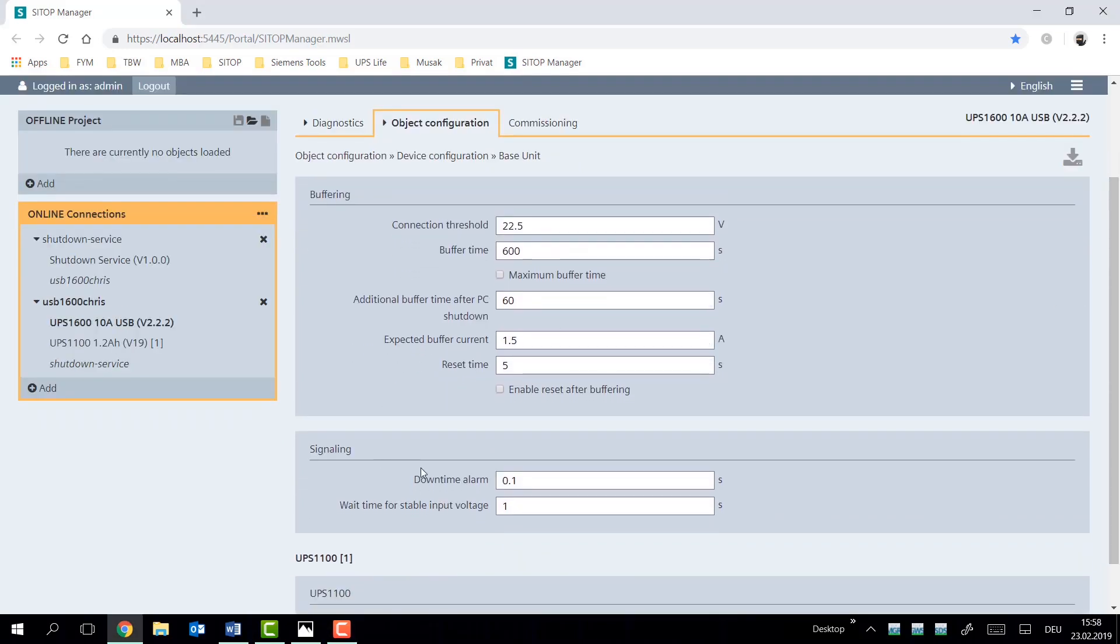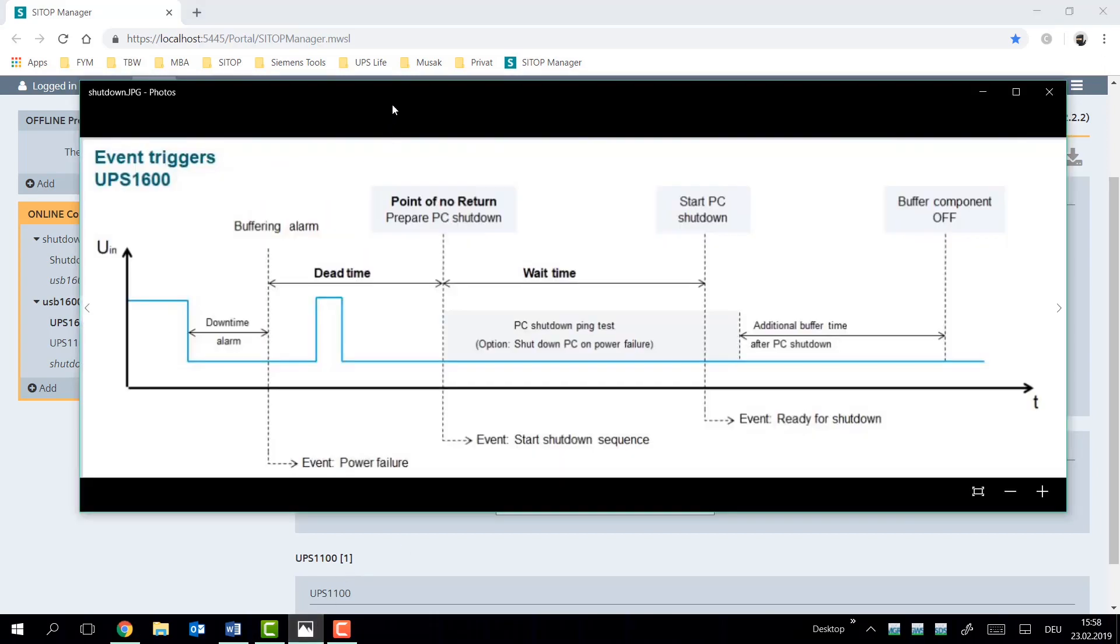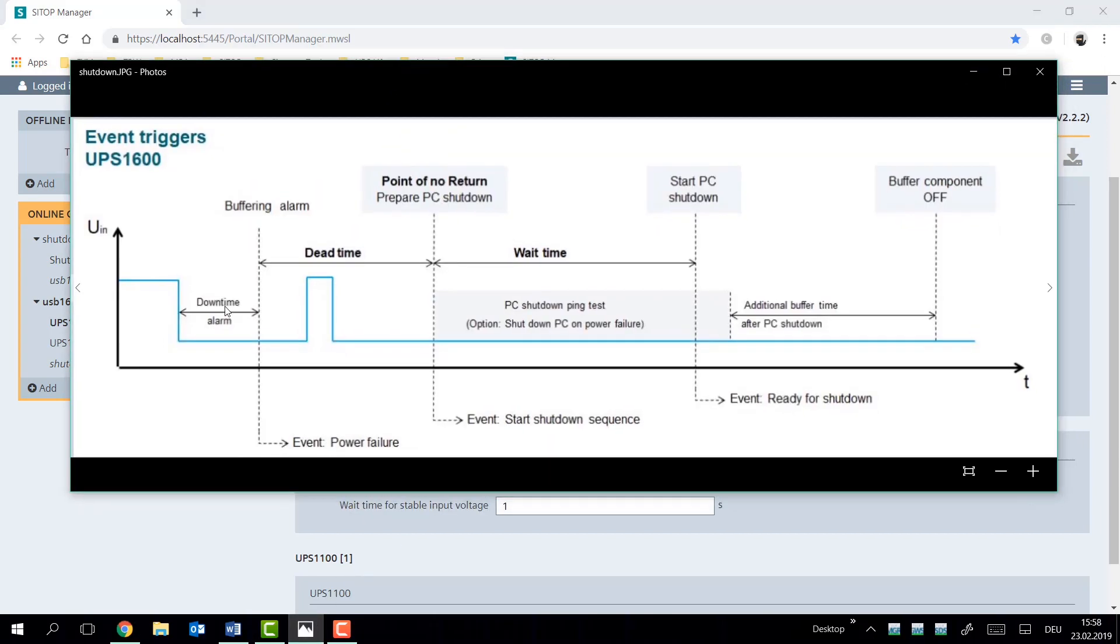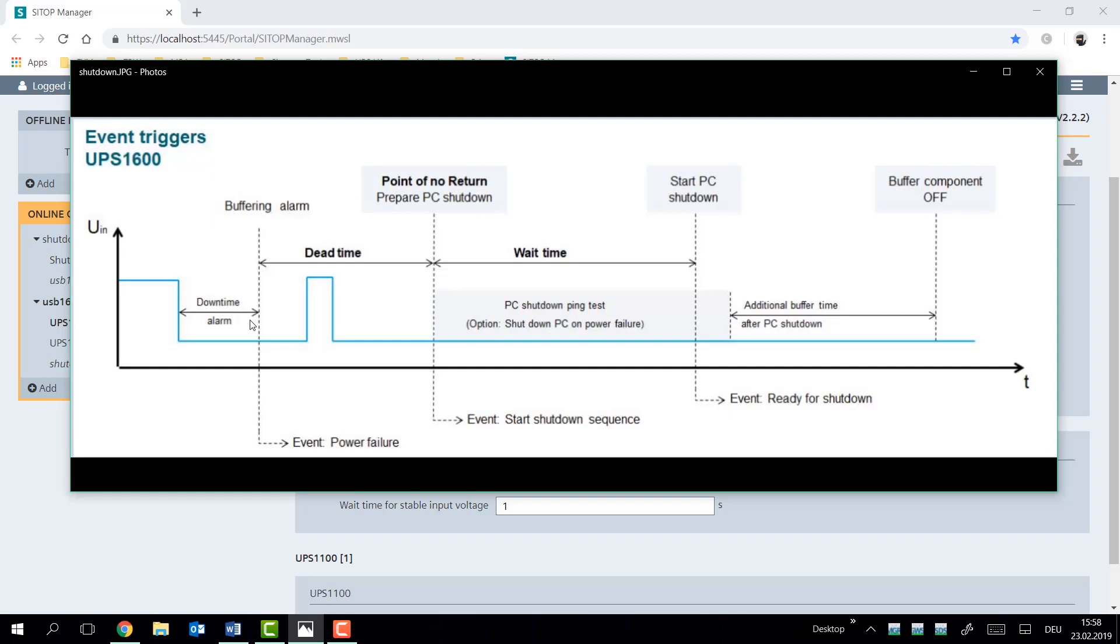Looking at the last two options we have under signaling, we have the downtime alarm and the wait time for stable input voltage. Again, going back to our shutdown diagram, this is very nicely displayed. The downtime alarm represents the time between the actual power failure and the buffering alarm setting on the UPS. Now, we set it as a default at 100 milliseconds. This reflects our buffering device. We also have buffer cells separately as a device. And this covers 80% of the typical fluctuations we see in a DC network.